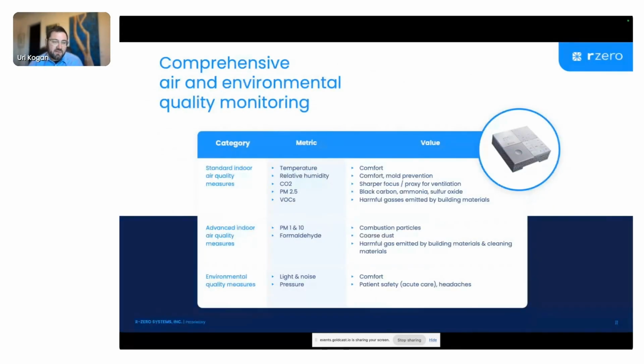Next, I want to talk about air and environmental quality monitoring. I've combined these into the same slide, highlighting 3 categories of measurements. The first is standard measurements like temperature, humidity, and carbon dioxide, about comfort — ensuring your HVAC system is delivering enough oxygen to people in your space. There are more advanced indoor air quality measures like smaller and larger particulate matter, for example 1 and 10 microns; the standard metric includes 2.5.